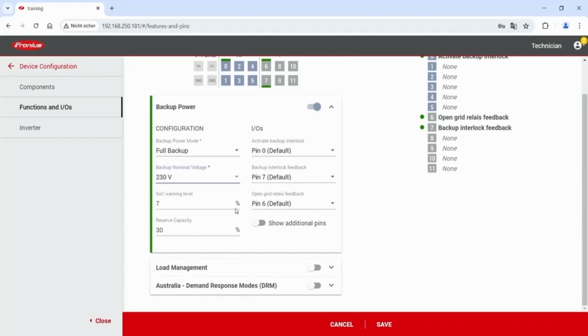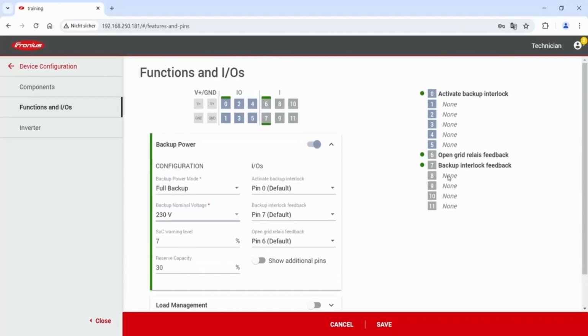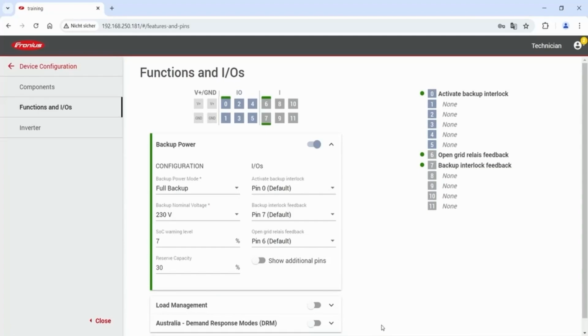So please make sure to configure all these three IOs, and when you are done you can check back the configuration on the right hand side of the page, and when you have that, hit the save button to conclude the commissioning. After this commissioning step, your solution is now ready to use, and you can now use the backup power functionality with your new Fronius backup controller.